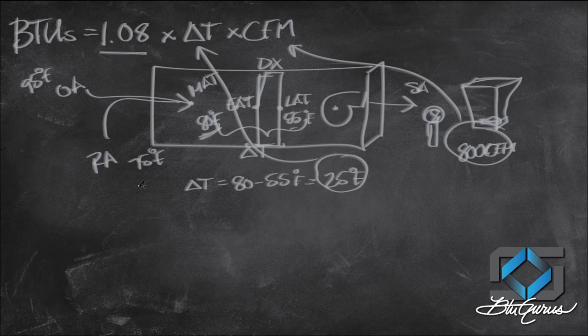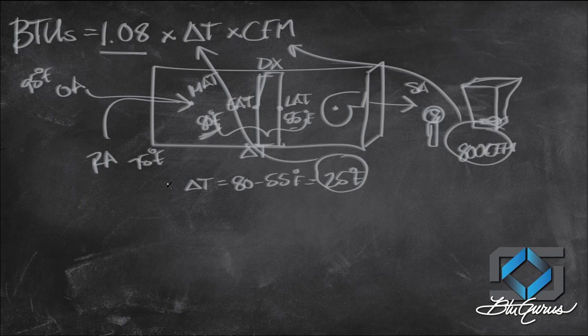Now I can calculate my BTUs of this equipment, and specifically this coil itself. Technically my supply air could be different than my leaving air, but whatever you want to measure, you can say it's either the unit or the coil. With all these numbers that I have, I'm going to calculate the BTUs.